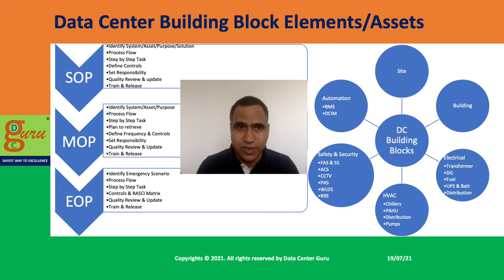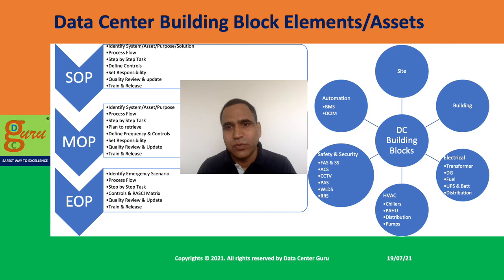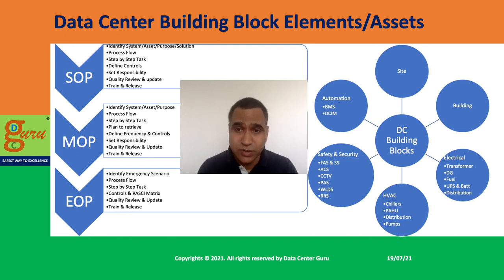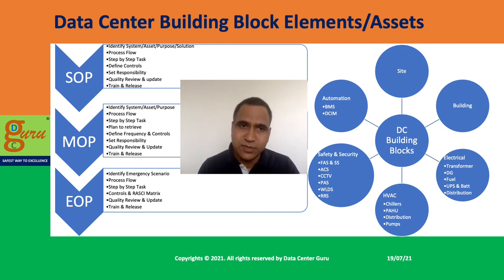So in sequential manner: first identify the system, asset, or purpose for which you are developing the process. Then develop a process flow. Then write step-by-step instruction-based tasks and activities. Define control points — where you need to check before moving to the next step, because if you don't check and move on, you may not be able to return and it has negative repercussions on data center operations. Set responsibilities clearly — who has to do what. Get the entire thing reviewed by the quality team, update if there is any change, train the people, then release it and let them start following it.